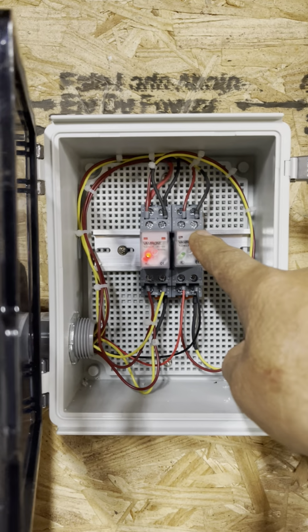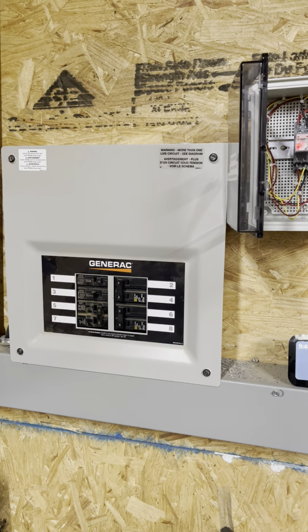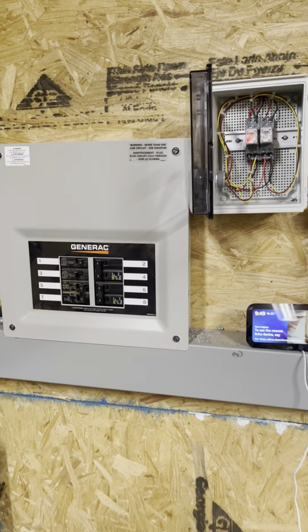Then the inverters, as the batteries come down, whether it's because of lack of solar or extreme usage, whatever, as the battery voltages drop to the set point, they say, oh, I need to start the generator. When they do, they trip this relay, which turns off the high voltage load feed coming in here. And so it fools the auto starter into thinking there's absolutely no power. So it starts up and transfers over. As soon as it transfers over, the XP6000s take care of managing the load from within the software in the inverter.